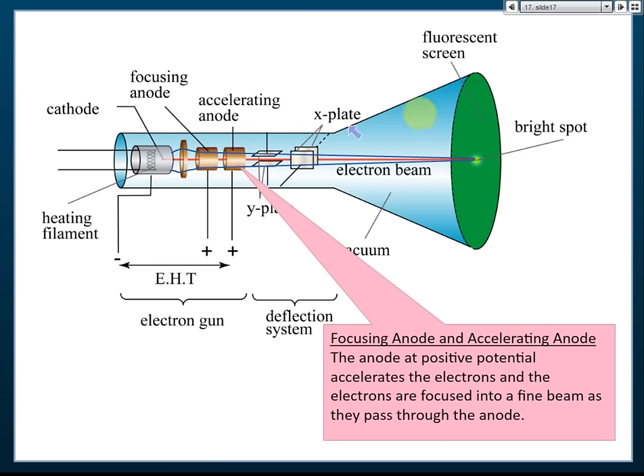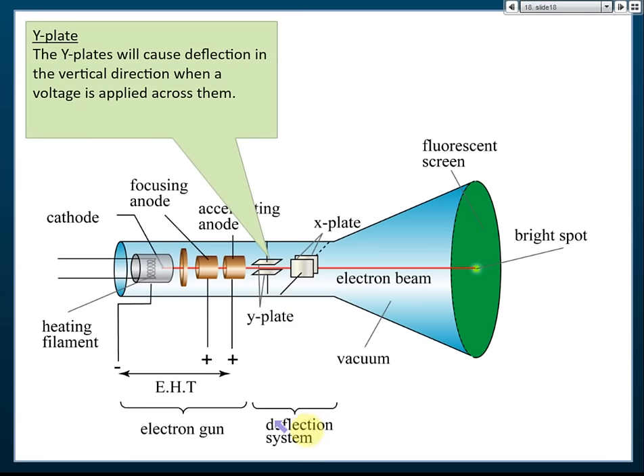The deflecting system has Y plates and X plates. The Y plates move the electron beam up or down. If the upper plate is positive and the lower is negative, the electron beam — which carries negative charge — deflects upward toward the positive plate. To deflect it downward, the polarity is reversed. The X plates deflect the beam left or right.